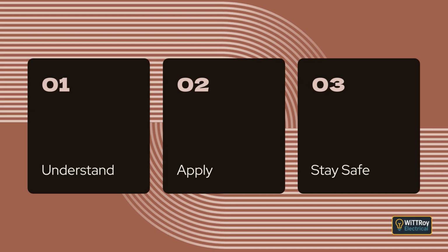An exception applies where pendant-type multiphase outlets with switching only in the active conductors are allowed when the outlet is not dependent on the supply cable for support, when additional mechanical protection is provided where necessary, and when the supply cable is selected to take into account any likelihood of vibration and movement expected during operation.